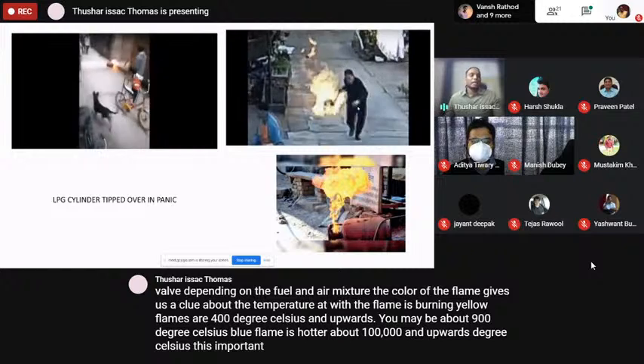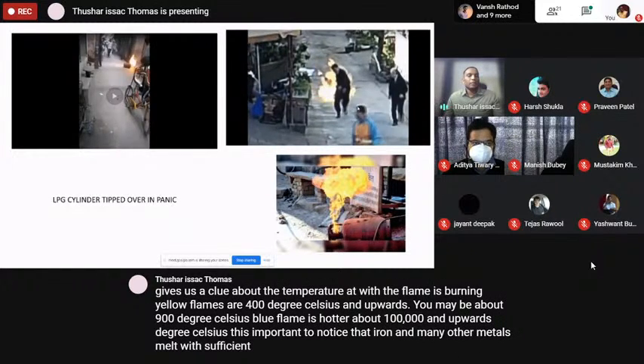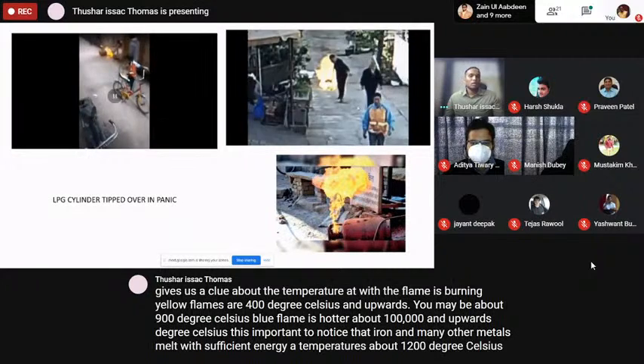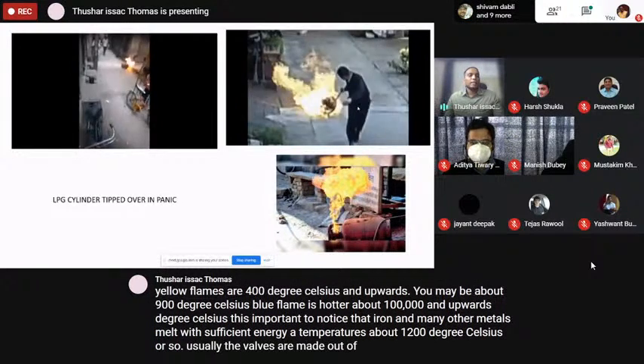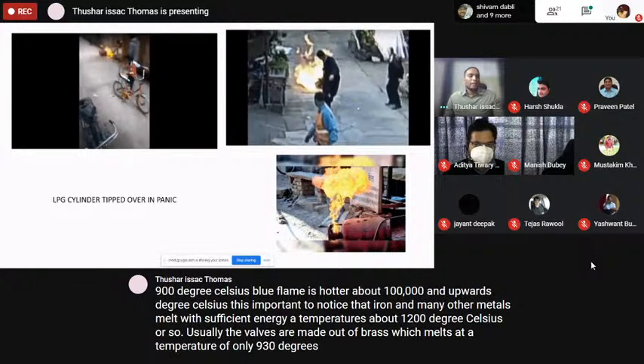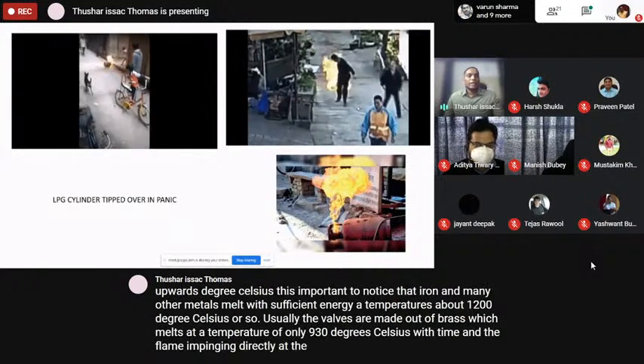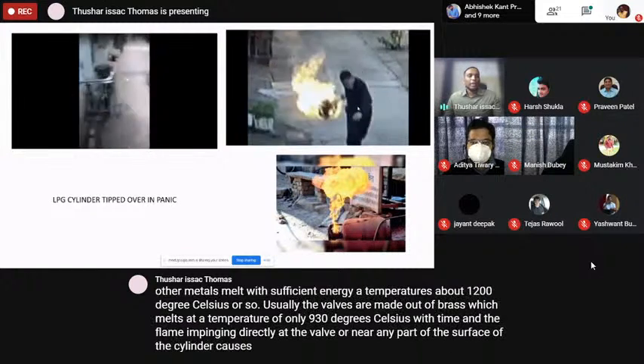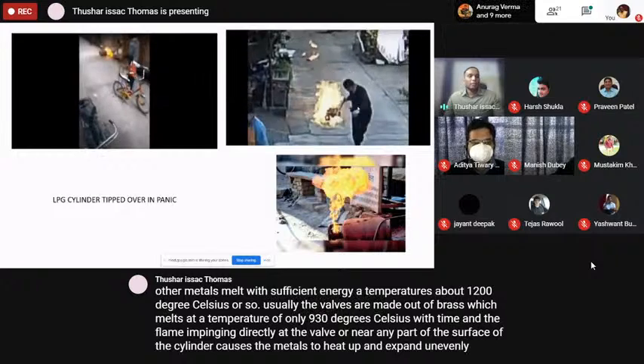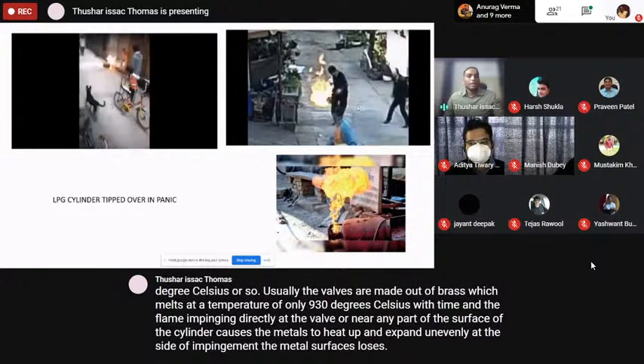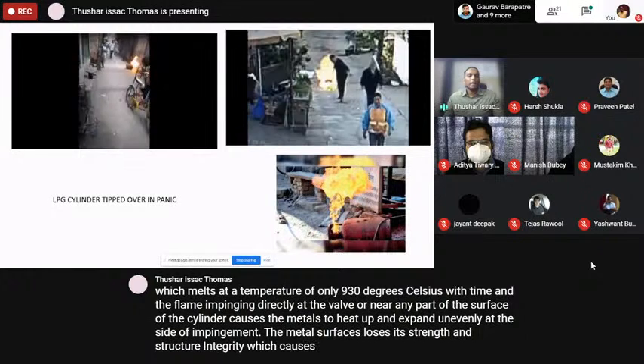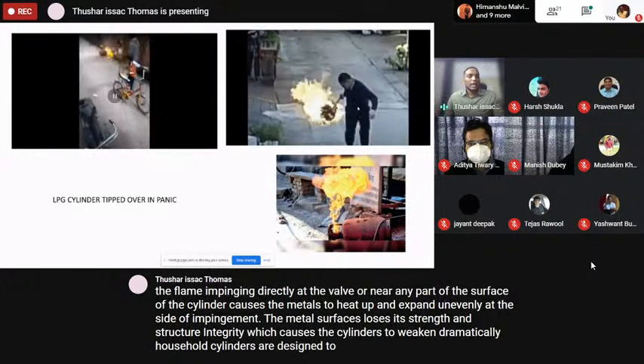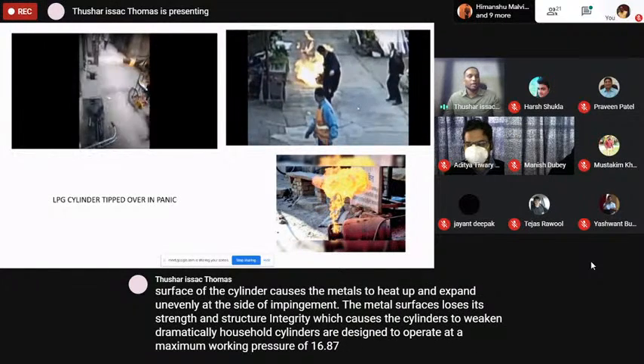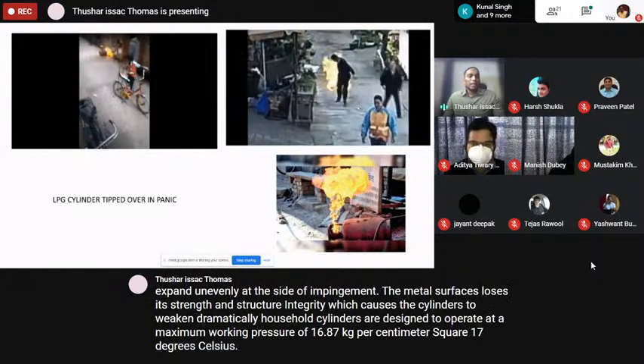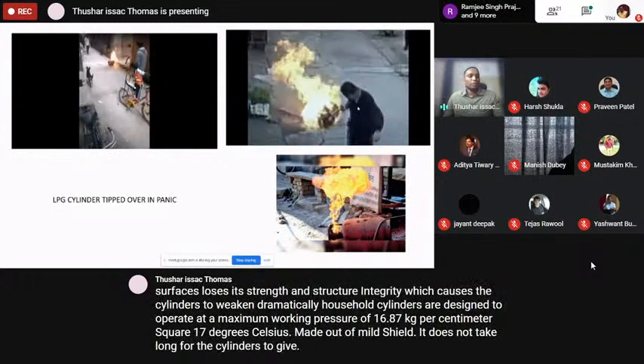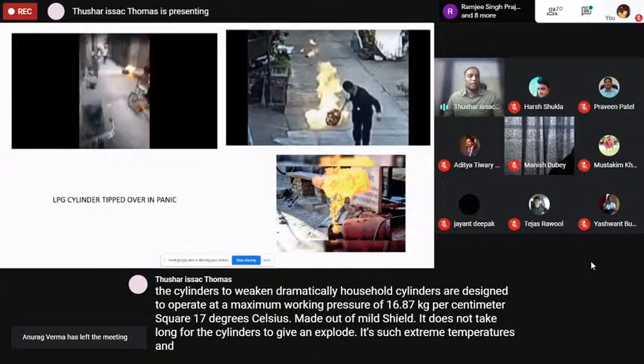It is important to notice that iron and many other metals melt with sufficient energy at temperatures about 1200 degrees Celsius or so. Usually, the valves are made out of brass, which melts at a temperature of only 930 degrees Celsius. With time and the flame impinging directly at the valve or near any part of the surface of the cylinder causes the metals to heat up and expand unevenly. At the site of impingement, the metal surfaces lose their strength and structural integrity, which causes the cylinders to weaken dramatically. Household cylinders are designed to operate at a maximum working pressure of 16.87 kg per centimeter square at 17 degrees Celsius. Made out of mild steel, it does not take long for the cylinders to give and explode at such extreme temperatures and compromise structural integrities.